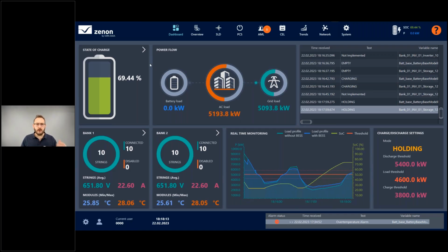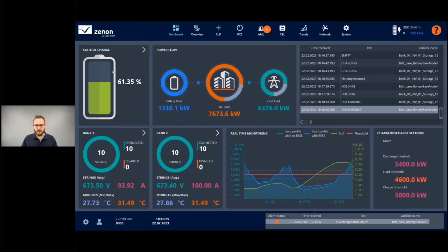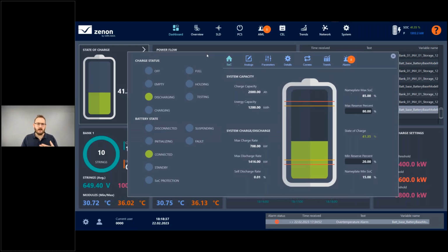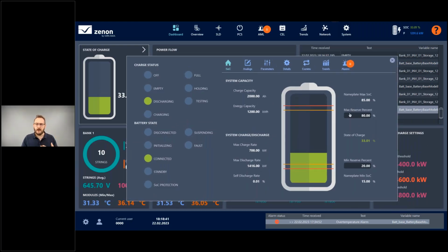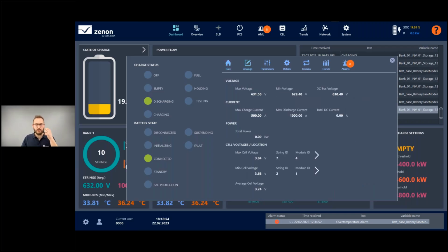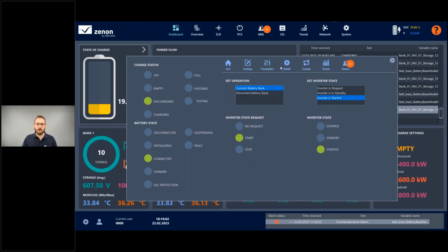One of the most important aspects when dealing with batteries is the state of charge of the battery system as a whole. In the top left, you can see a representation of the state of charge of the system. An operator, if required, would then need to drill down for additional information on the state of charge - changing the set points for max or min percent of charge or discharge, depending on the situation. They would also monitor critical information such as voltages, currents, and other parameters for starting or stopping, or taking the system in its entirety out of commission if required.